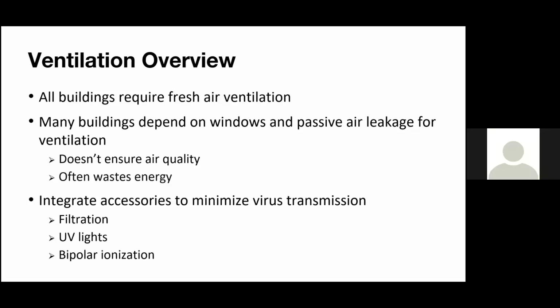And transitioning into ventilation, kind of to state the obvious here, all buildings require fresh air ventilation of some form, right? So, 10, 15 years ago, we would actually depend on windows and passive air leakage for ventilation, which I can tell you right now is very, very inefficient, right? It's going to often waste energy. You're just bringing in raw air at, say, 20 degrees, right? What does that mean? That means your HVAC system, your heat pump system, has to be completely upsized in order to meet that temperature, because you're constantly going to be fighting with the windows if you're leaving your heat pumps on, or even the passive air leakage. And also something to note is, it doesn't ensure air quality whatsoever.